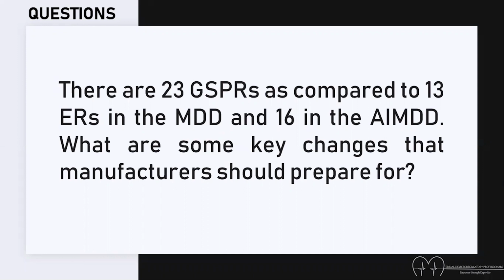And the first is on the chemicals, toxicity, and basically also biocompatibility properties. And that aligns also with the new edition of the biocompatibility standard that has just been released, where the new thinking and expectation from notified bodies is that what we've always done is not good enough anymore. What we've done in the past is we used Annex 1 of this standard, or Part 1, which is a table indicating which test you have to do depending on the level of invasiveness and the length of interaction between a medical device and the patient. And that determines your program.